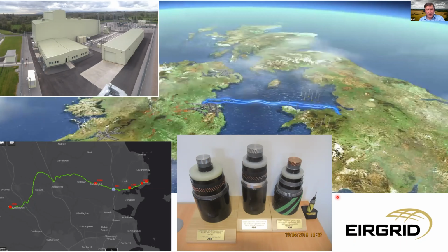Fiber optic cables, this fiber optic cable here, are bundled with the power cables and allow for robust communications between the converter stations. It also allows for fast acting response to system events such as frequency control. And the fiber connection also provides a resilient communication path that the TSOs can use and rely upon during blackouts. We also use the fibers for DTS monitoring of the cable with a number of redundant fibers. And there's also a commercial fiber lease with Geo Networks.